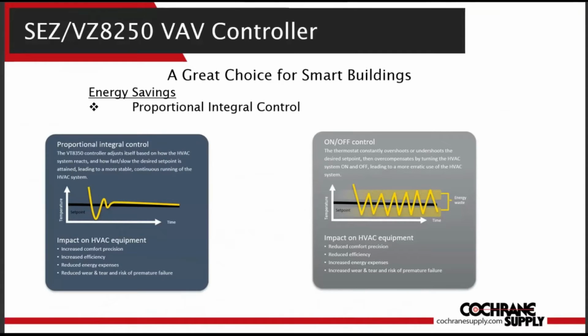These are another aspect of the 8250 room controllers that make them a great choice for smart buildings. Thermostats typically use an on-off strategy, on the right side of the screen. When the space temperature rises above or drops below the set point, the heating or cooling comes on and does not turn off until reaching the set point. The result is overshoot, where the space is overheated or overcooled, leading to wasted energy, not to mention uncomfortable occupants and more wear and tear on the mechanical equipment.